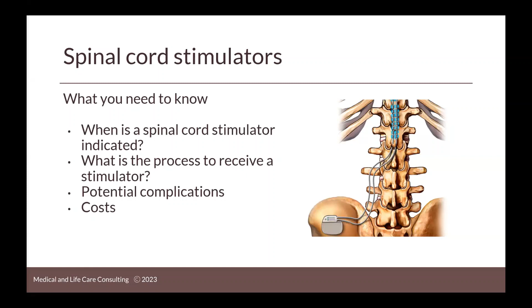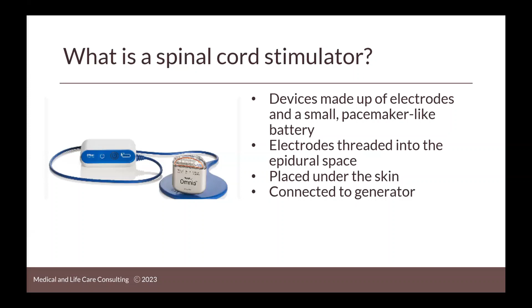So a spinal cord stimulator is made up of electrodes, thin wires, and a small pacemaker-like battery pack, the generator. The electrodes are threaded up the epidural space, placed between the spinal cord and the vertebrae. I've had patients where the physician has not found that there's enough room in the epidural space, and they have to implant them percutaneously, and so that's the physician's decision. The generator is placed under the skin near the buttock or abdomen, and the electrodes are connected to the generator. An external controller can then be used to turn the generator on and off, initiating electrical impulses when they feel pain.